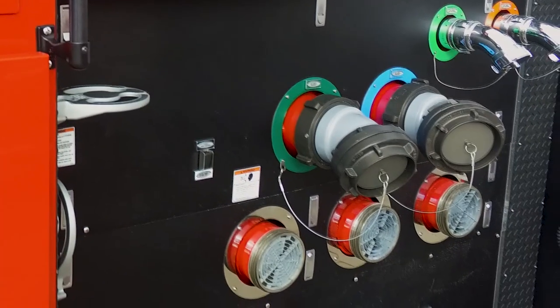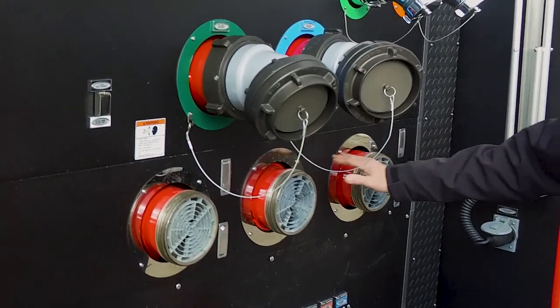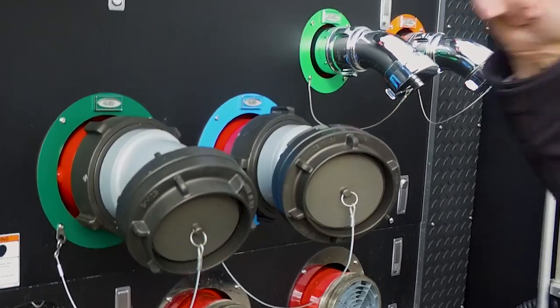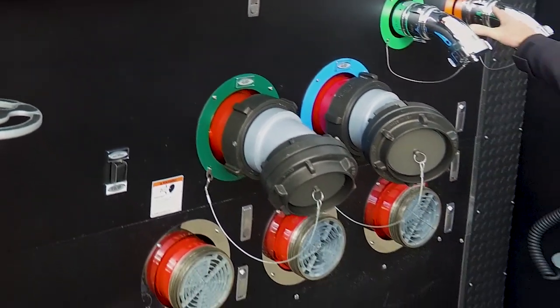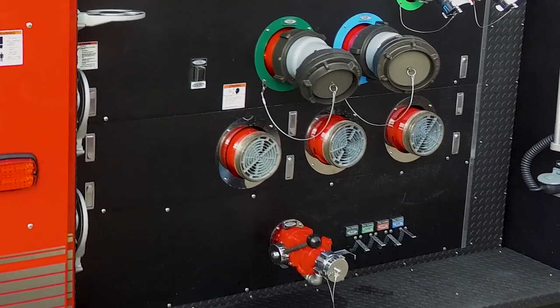As you get to this side of the pump house, you'll see the business end of that big water pump. You've got three six-inch suctions to supply water to the pump. The pump then discharges water out of the aerial, out of the two-and-a-half-inch outlets, and at the rear you've got two two-and-a-half-inch on the passenger side as well as two six-inch large-diameter discharges to take care of your discharge needs.